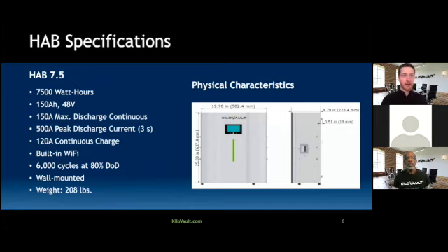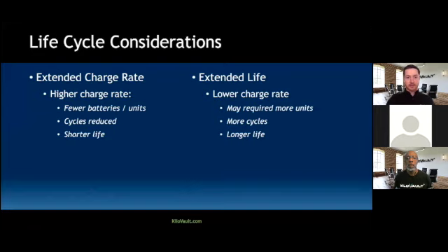Something notable about these batteries is their built-in Wi-Fi communication, so they can securely report data to the cloud. We have a 6,000 cycle life rating at 80% DOD, and it is a wall-mounted battery. So you'll see the right picture shows the mounting flange on the back of the battery. And it is a hefty battery at 208 pounds, definitely a two-person job at least to get it up on the wall.